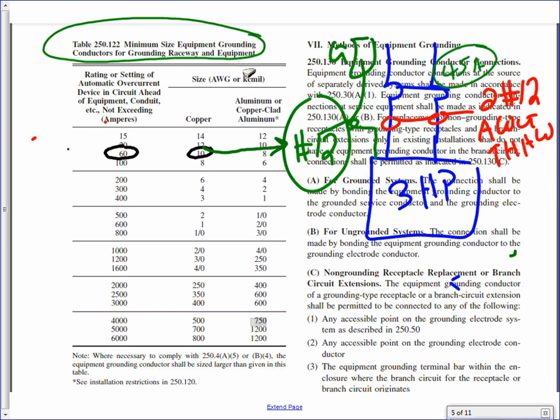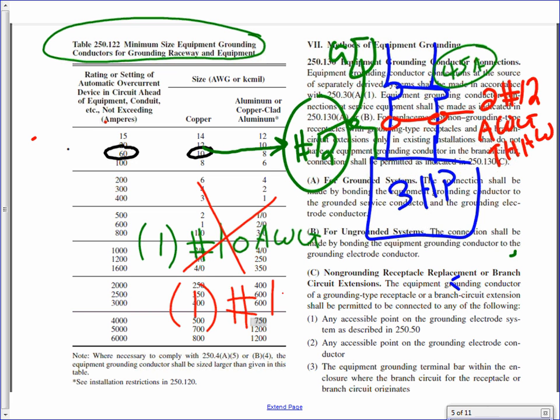The code says, guys, the equipment grounding conductor does not need to be larger than the ungrounded conductor. So I know I came up with one conductor number 10, right? One conductor number 10 AWG. But the code says then what you need to do, you need to cross that one out, and you don't need to go larger, and make it one conductor number 12 AWG.